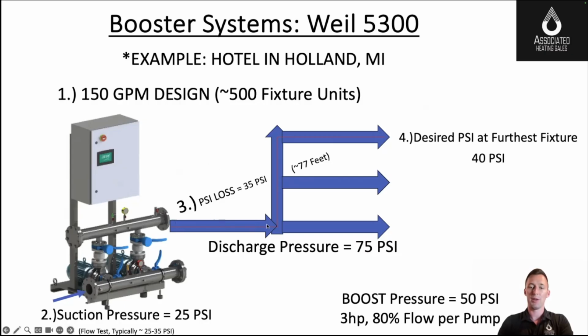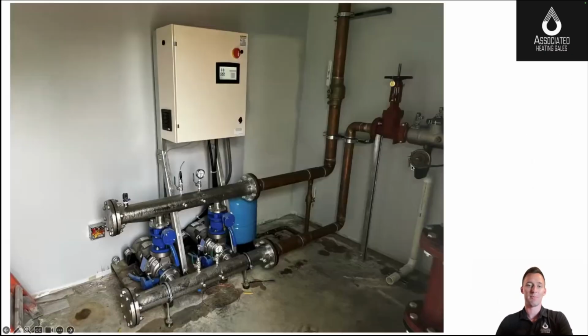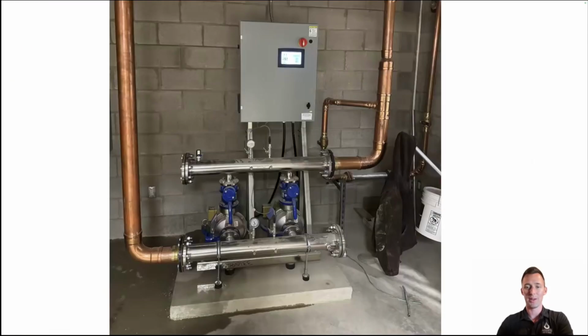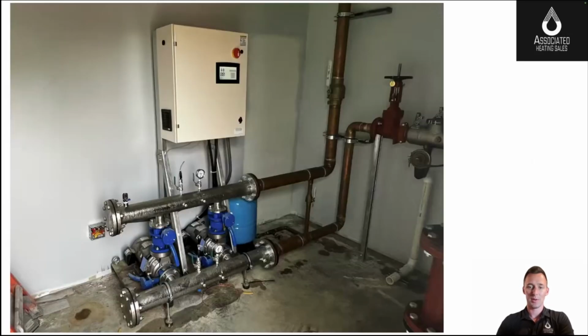But we know in that final run, or that critical path, we'll call it, we're going to lose 35 PSI. And we'd love for that final fixture to have 40 PSI. So our discharge manifold needs to be at 75 PSI at all times. And so the difference here between the discharge and the suction is 50. So we're going to call that boost pressure. Listing all these numbers in a schedule would be ideal. It helps us kind of figure things out. Example of how that ended up looking here. And another one at an early childhood center. So a couple nice installs here.